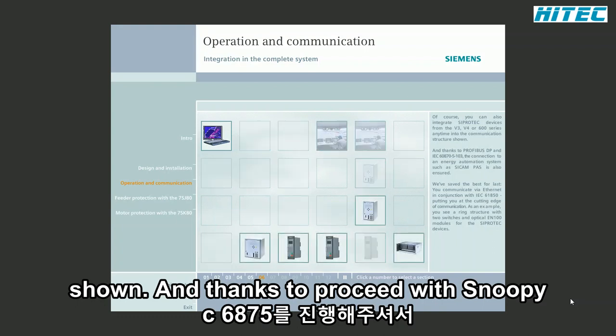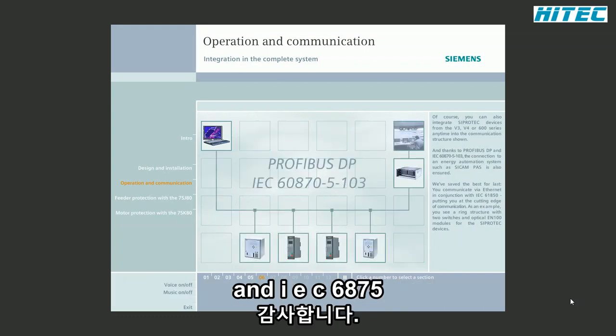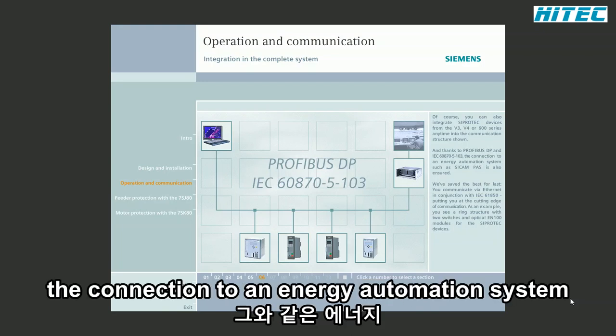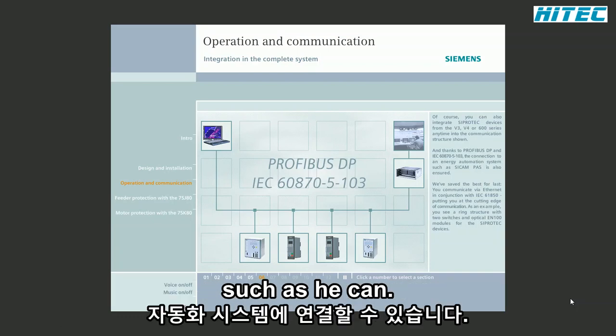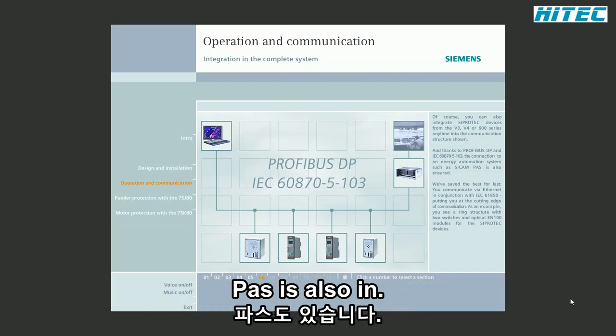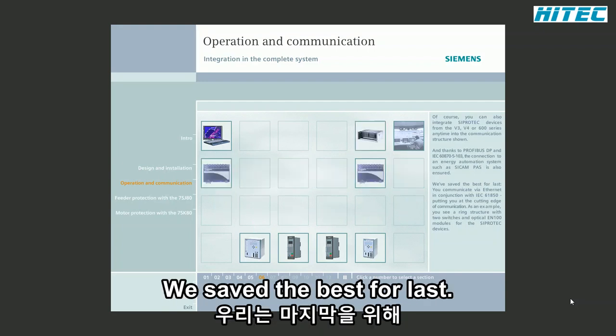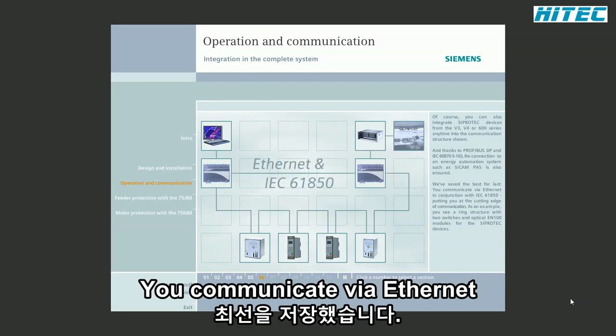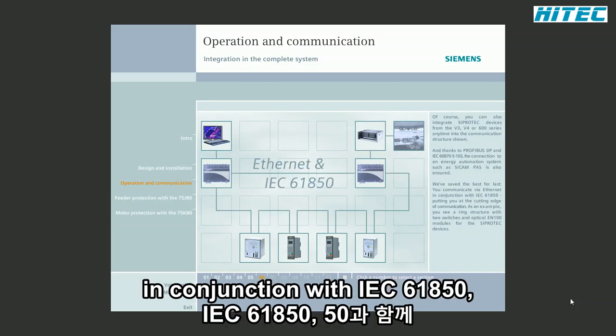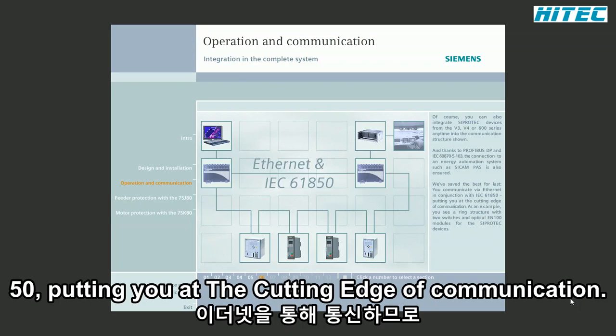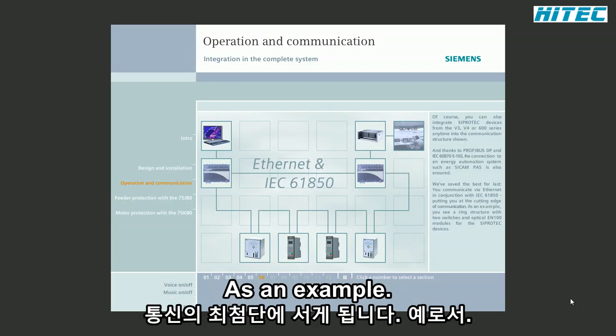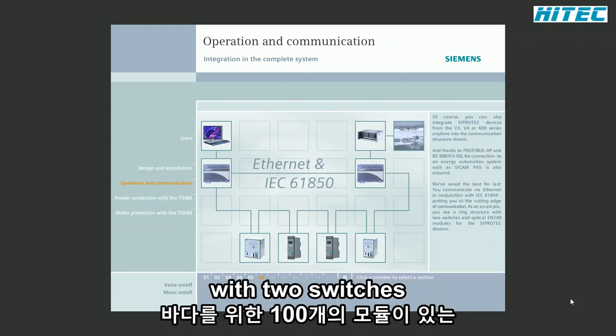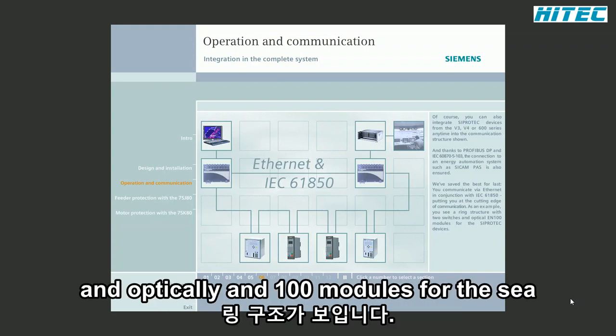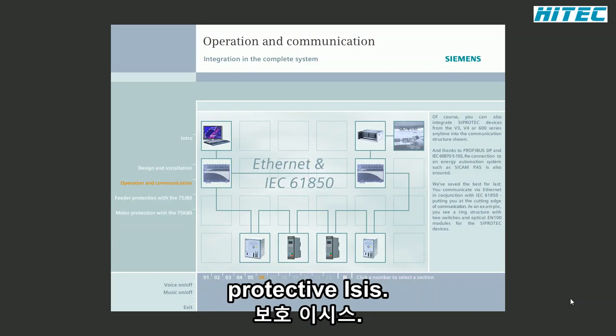And thanks to Profibus DP and IEC 60870-5-103, the connection to an energy automation system such as SICAM PAS is also ensured. We've saved the best for last. You communicate via Ethernet in conjunction with IEC 61850, putting you at the cutting edge of communication. As an example, you see a ring structure with two switches and optical EN100 modules for the SIPROTEC devices.